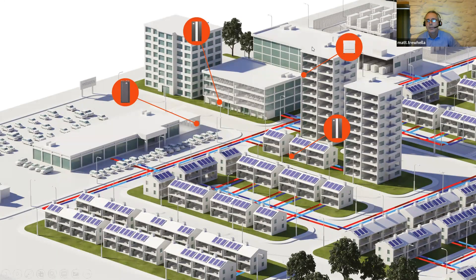On a city scale, tiny apartments have a small heat pump, larger buildings a domestic size, and a supermarket or office blocks a commercial-grade heat pump. The network of pipework shares all that energy, turning on and off at slightly different times. Each building has a heat pump suited to its own environment — some at 35 degrees with underfloor heating, some on radiators at 50 degrees, some doing hot water at 60 degrees. The network runs between 0 and 20°C, and the heat pumps do all the upgrading inside the thermal envelope of the building.